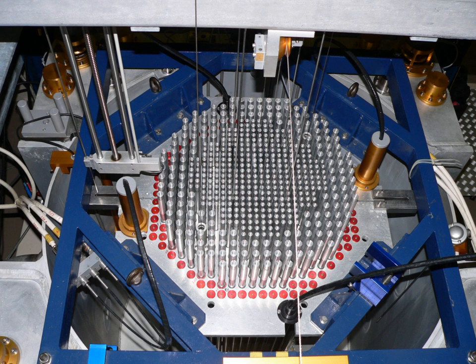The Pebble Bed Reactor, a high-temperature gas-cooled reactor, is designed so high temperatures reduce power output by Doppler broadening of the fuel's neutron cross-section. It uses ceramic fuels so its safe operating temperatures exceed the power reduction temperature range. Most designs are cooled by inert helium. Helium is not subject to steam explosions, resists neutron absorption leading to radioactivity, and does not dissolve contaminants that can become radioactive.